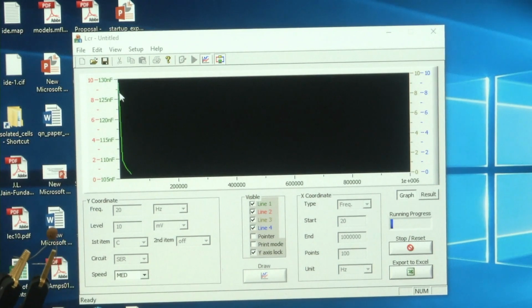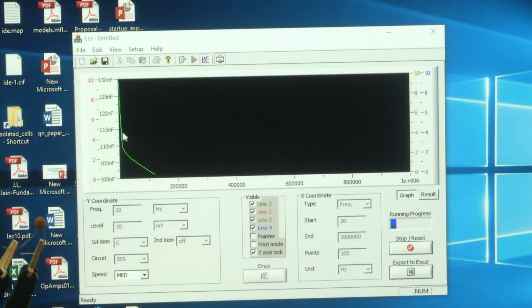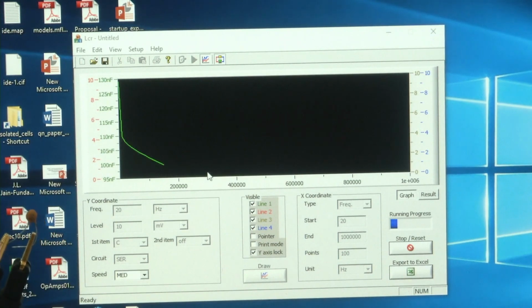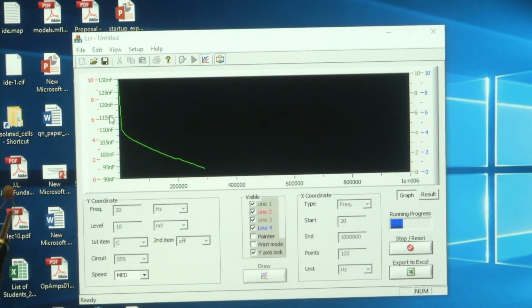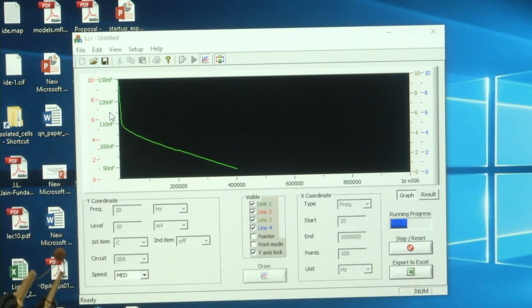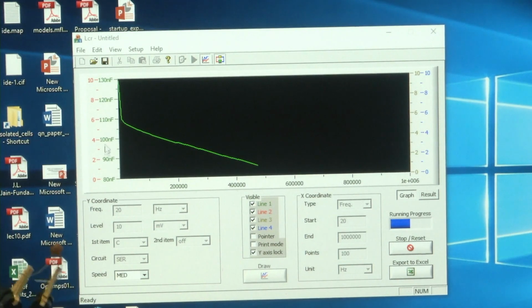So, you can see how the capacitance value is varying across the frequencies, and it is plotting it out also. Within the operational conditions of this capacitor, most of the values will lie within a tolerance level, between 100 nanofarad and 130 nanofarad, around the actual value the capacitor is designed for, that is 0.1 microfarad. As it crosses its stated operating condition or frequency level, it will start coming down. We are going to measure till 1 megahertz, taking 100 points.